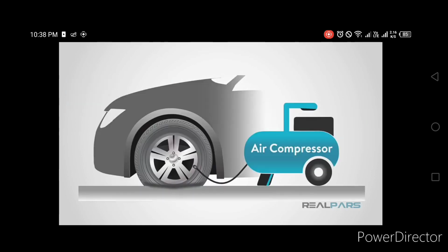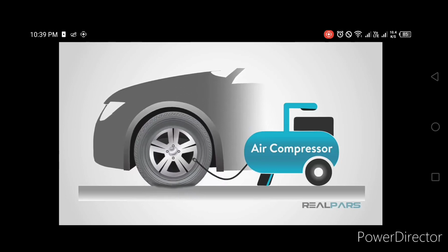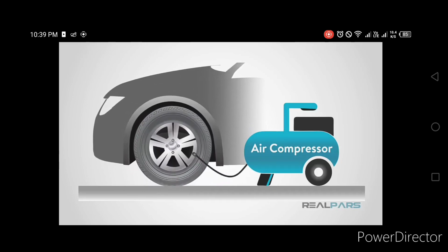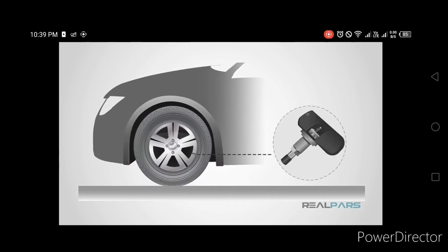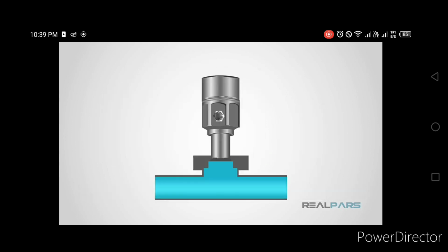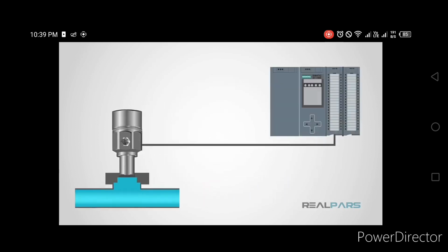The pressure of the air in your tire is a great example of pressure and how it's measured. As we air the tire up, the force it exerts on the tire increases, causing the tire to inflate. This is monitored with a pressure sensor inside the tire on newer vehicles. So how does a pressure sensor work? In a nutshell, it converts the pressure to a small electrical signal that is transmitted and displayed. These are also commonly called pressure transmitters because of this.